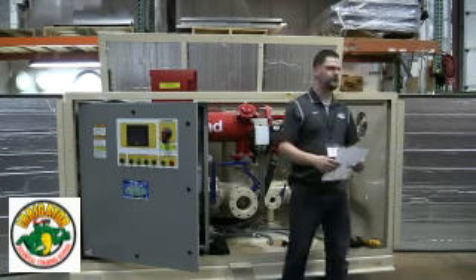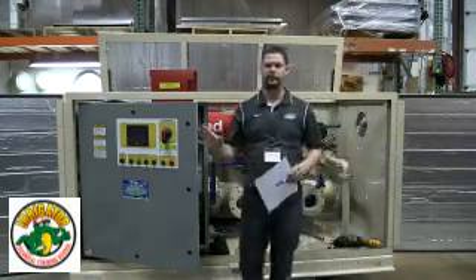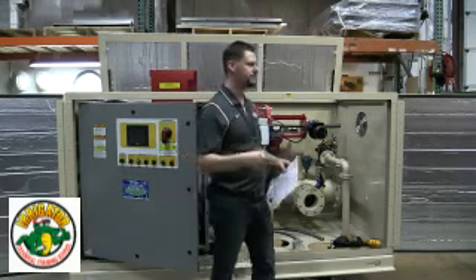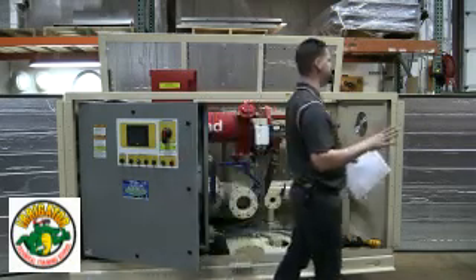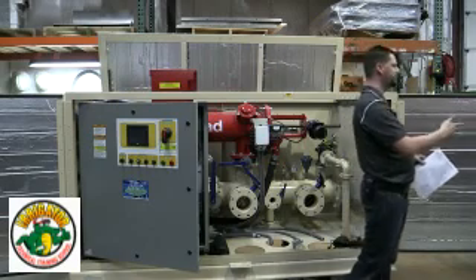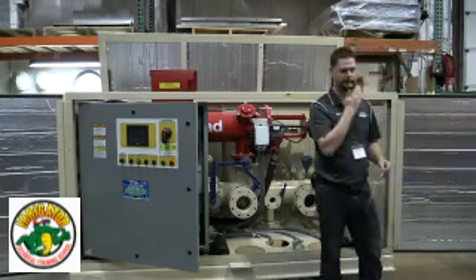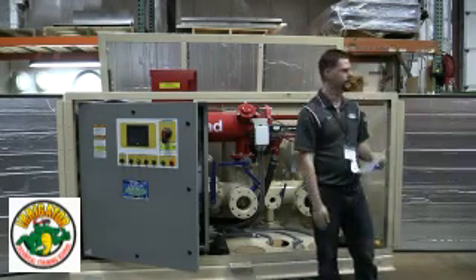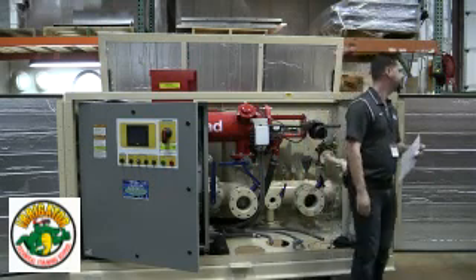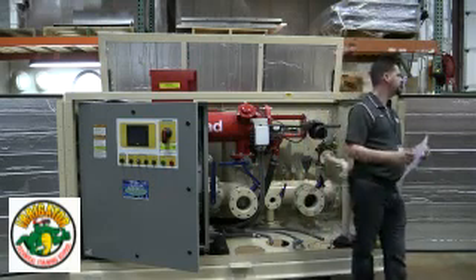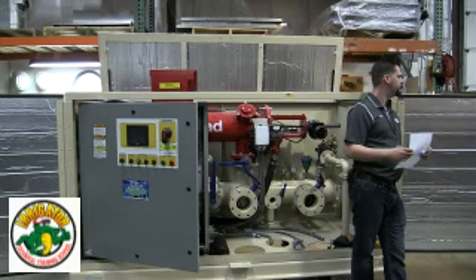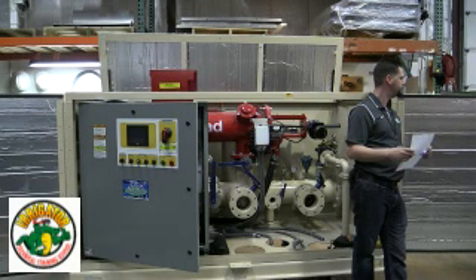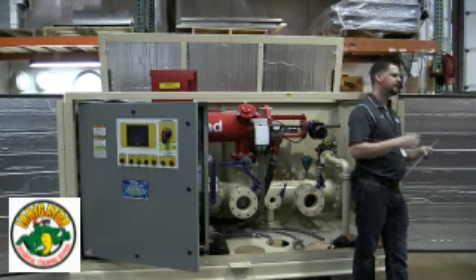There it is. So, does anybody have questions on winterization, startup? Does anyone feel I looked over something? I know there's some people in here that are probably thinking, man, I totally skipped over the... you know, like when you're testing your pumps, deadhead amp checks, full load amp checks. When the pumps are running, you basically look, listen, and feel. Do you hear bearings squeal? Does it vibrate? Is there water spraying out of some place there shouldn't be spraying? That's always a bad thing.